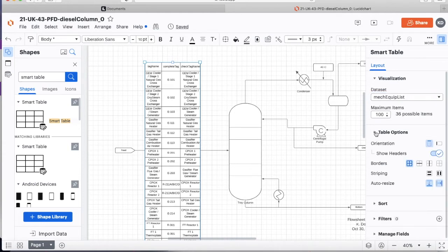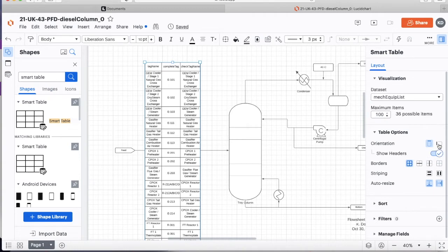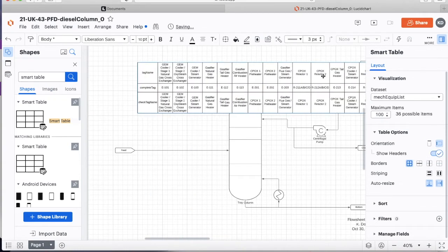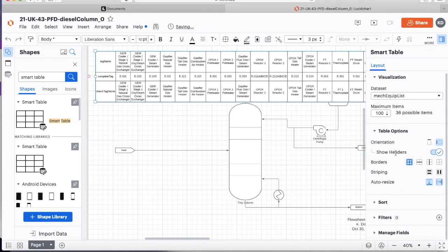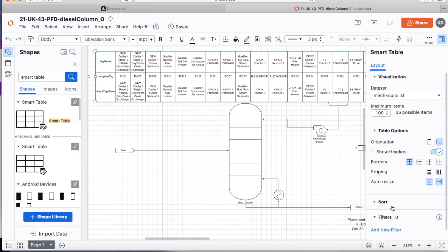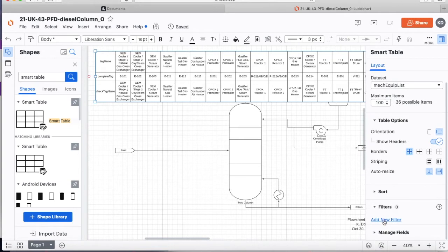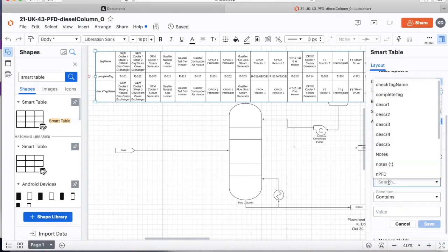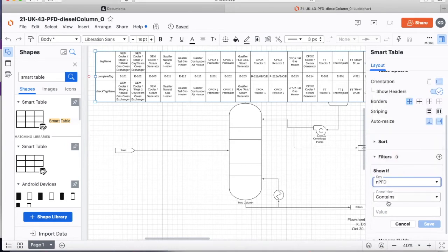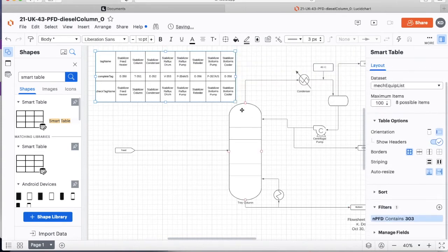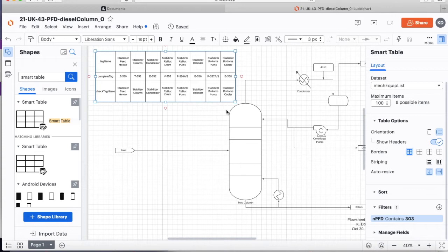The first thing I want to do is I want to put it sideways. Okay, well that's better. But it's got a bunch of equipment that I don't care about in my mechanical equipment list. So I need some filters. The first thing I'm going to filter is I'll say add a new filter. And I'm only going to show if. I've got one of the columns is npfd. So I'll say show if npfd contains 303. And voila. Now I've only got the data in my mechanical equipment list that has the field for the drawing number 303. So now I've got just that data.